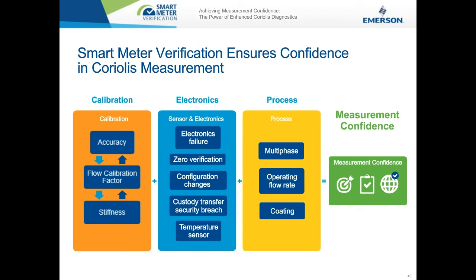Are all the Coriolis meters calibrated at factory? Is a calibration report provided? Yes, they sure are. We have a number of flow labs around the world. They are all accredited and traceable to ISO 17025. That's a NIST designation, and we're audited by an agency called NVLAP. A report is sent with each meter, and we also maintain records here at the factory.